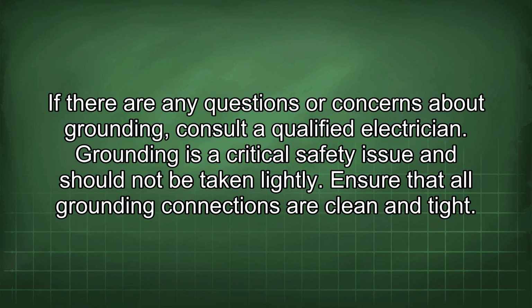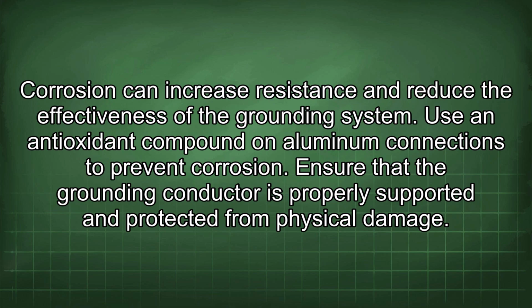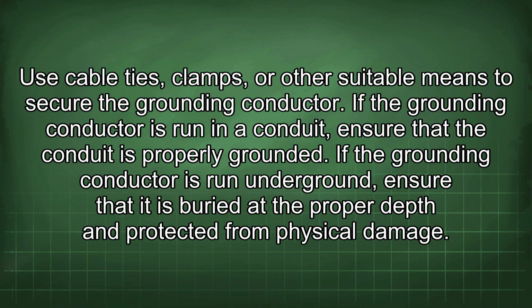Grounding is a critical safety issue and should not be taken lightly. Ensure that all grounding connections are clean and tight. Corrosion can increase resistance and reduce the effectiveness of the grounding system. Use an antioxidant compound on aluminum connections to prevent corrosion. Ensure that the grounding conductor is properly supported and protected from physical damage. Use cable ties, clamps, or other suitable means to secure the grounding conductor.